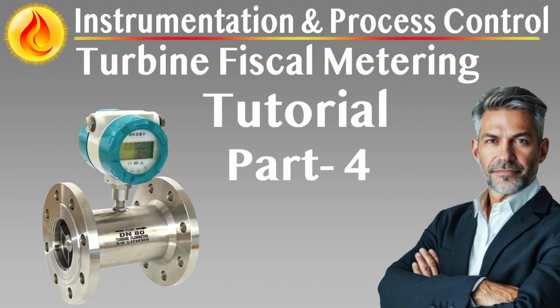The stream microcomputer must receive dual pulse inputs from the turbine meter pickups and execute real-time pulse integrity verification. These checks must detect any discrepancies in pulse timing or count that could indicate signal degradation, pickup failure, or meter malfunction. The system must comply with industry-recognized standards for pulse verification, including detection of missed, duplicated, or distorted pulses.